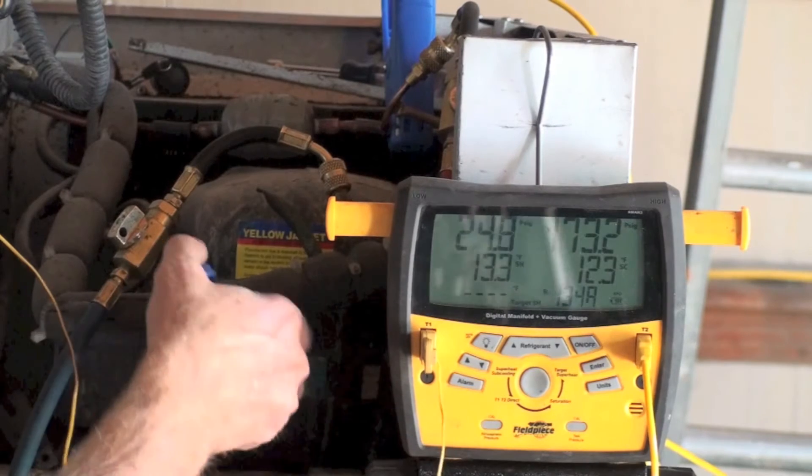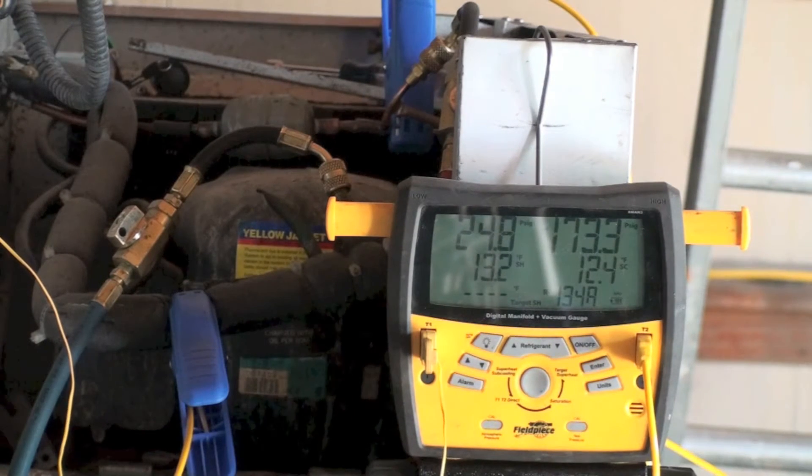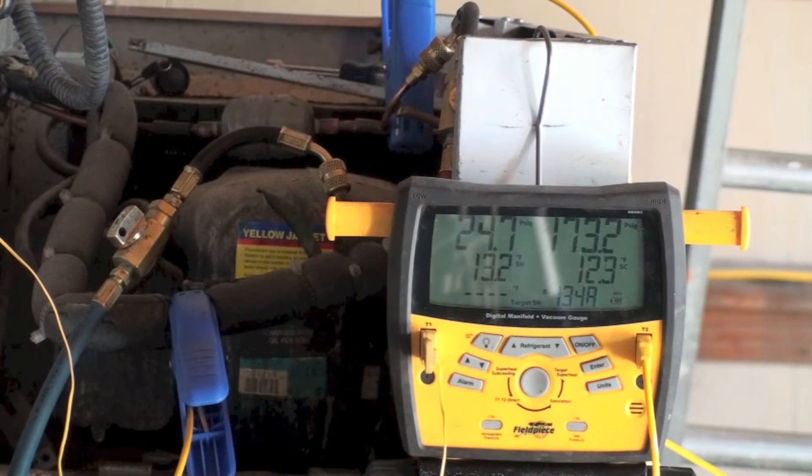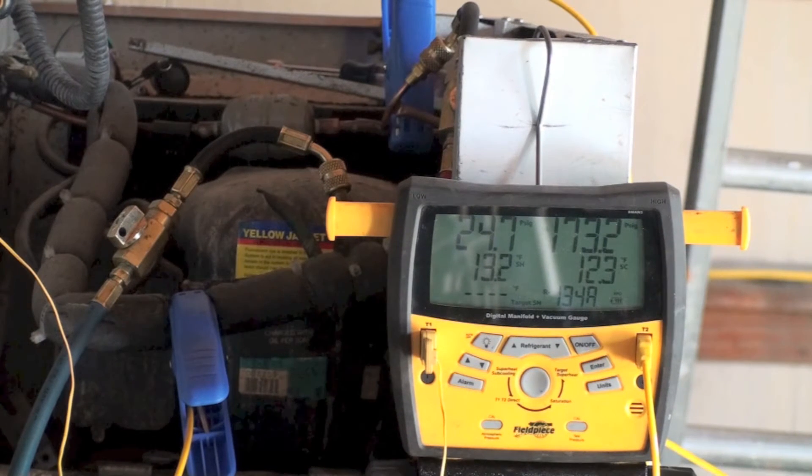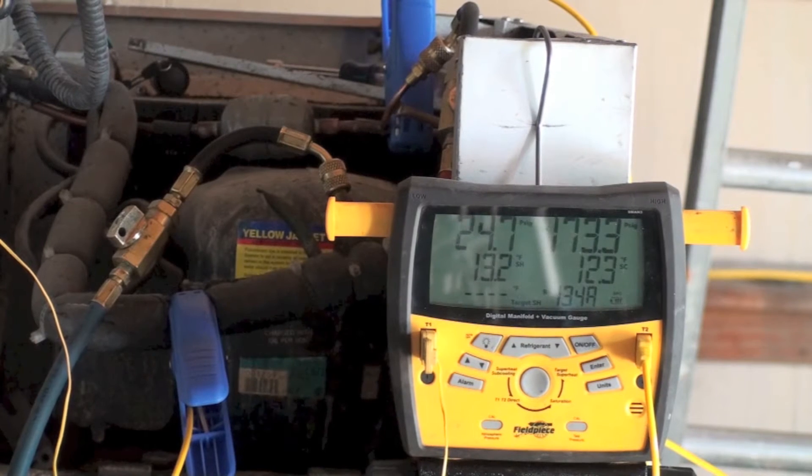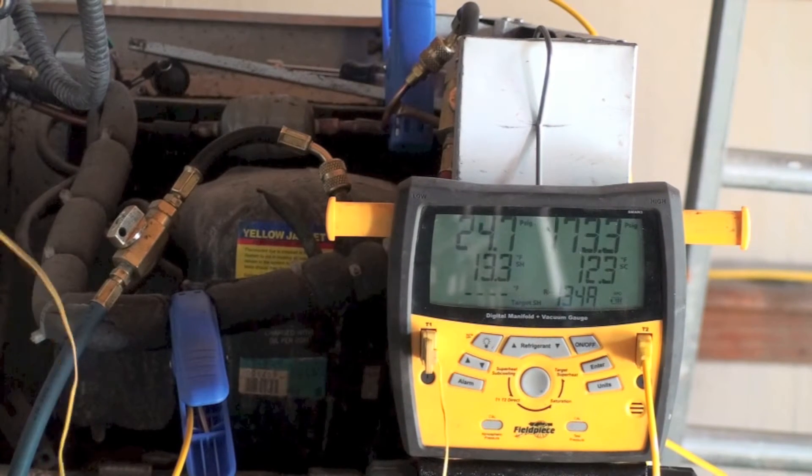I've got the regular probe right here. That's on the suction line about halfway between the evap and the compressor. I'll show you where I put it inside here.